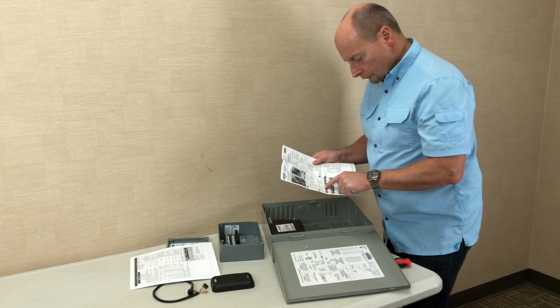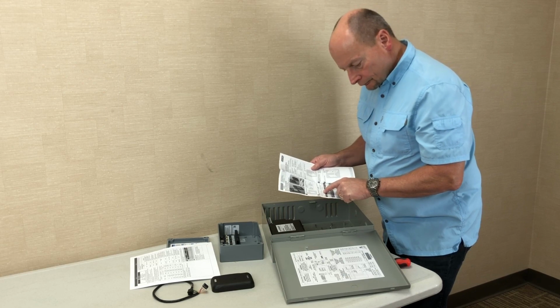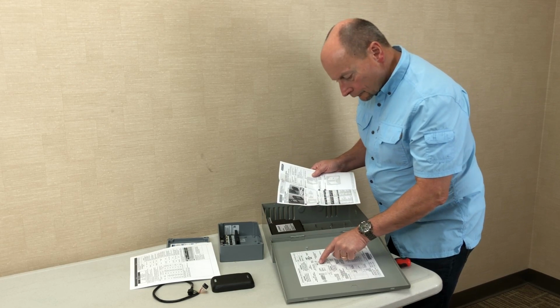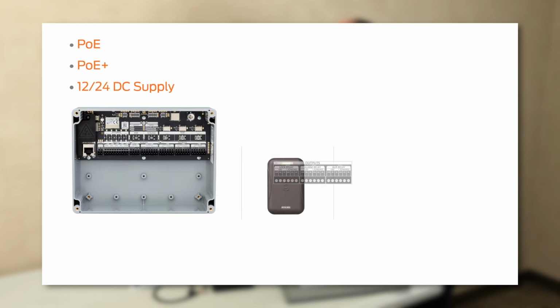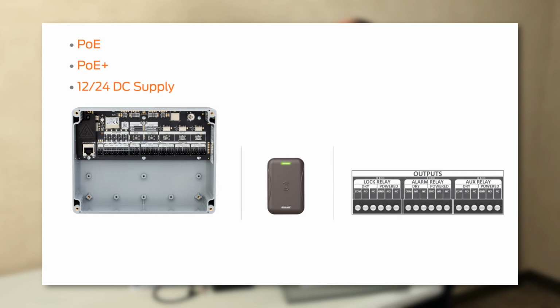Prior to installation, confirm that your power source will be sufficient for your devices. The CTE can be powered by Power over Ethernet, or PoE, PoE Plus, or a UL-listed 12 or 24 volt DC power supply. The CTE can provide power to the included credential reader and to the three outputs labeled Lock Relay, Alarm Relay, and Aux Relay.